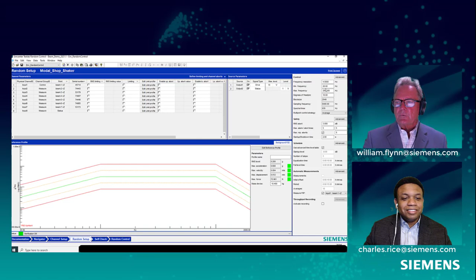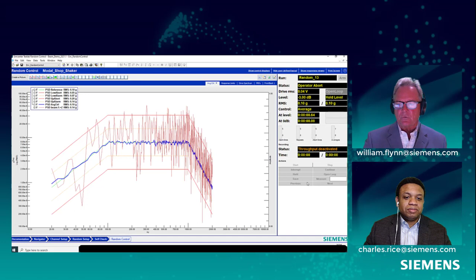So I've got, in this case, my stable averages per loop is 5. I've got a very low exponential weighting factor, which results in a degrees of freedom of only 10. So we'll see what influence that has and how the control works with that. First, I have to run the self-check. So I'll show the self-check procedure here.